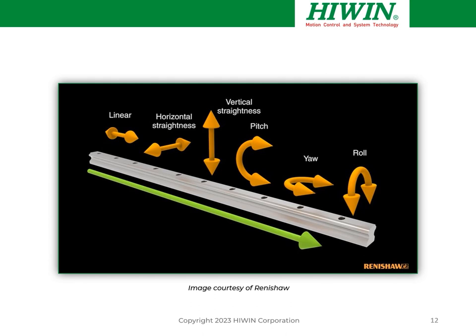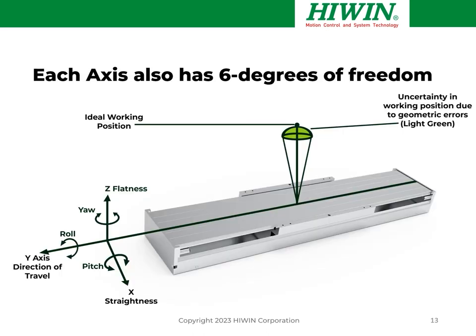Here's another illustration of the six degrees of freedom. Anything other than straight-line linear motion results in positioning errors in the overall motion system. We can see travel along a linear guideway bearing showing the desired direction of travel, horizontal and vertical straightness, and the three angular components — pitch, yaw, and roll. When we build an axis from these components, that axis itself also has six degrees of freedom. Linear stages have errors that result from the combination of component tolerances used to build the stage, creating some uncertainty in your working position due to geometric errors.